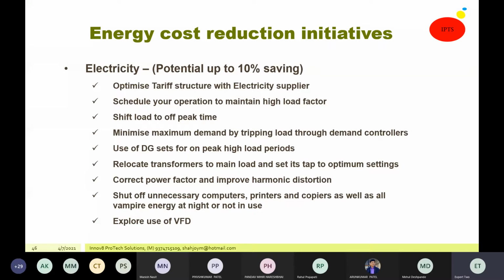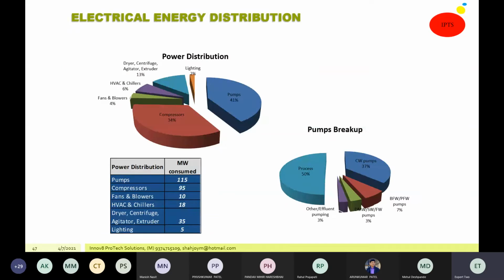Then you have to correct the power factor and harmonic distortion, and shut off unnecessary loads, because all these computers and other consumers are non-linear loads. So it may lead to a reduction in the power factor as well as harmonic distortion. And use VFDs. Nowadays VFD cost is very low, and in most places people are exploring the use of VFDs so that energy consumption can be reduced. If you see the distribution of electrical energy consumption in major industry, about 41% goes to the pumps, 34% to the compressors, then dryers, agitators, extruders about 13%. So the pumps and compressors are the major areas where we have to focus and find out whether we can reduce the energy consumption.